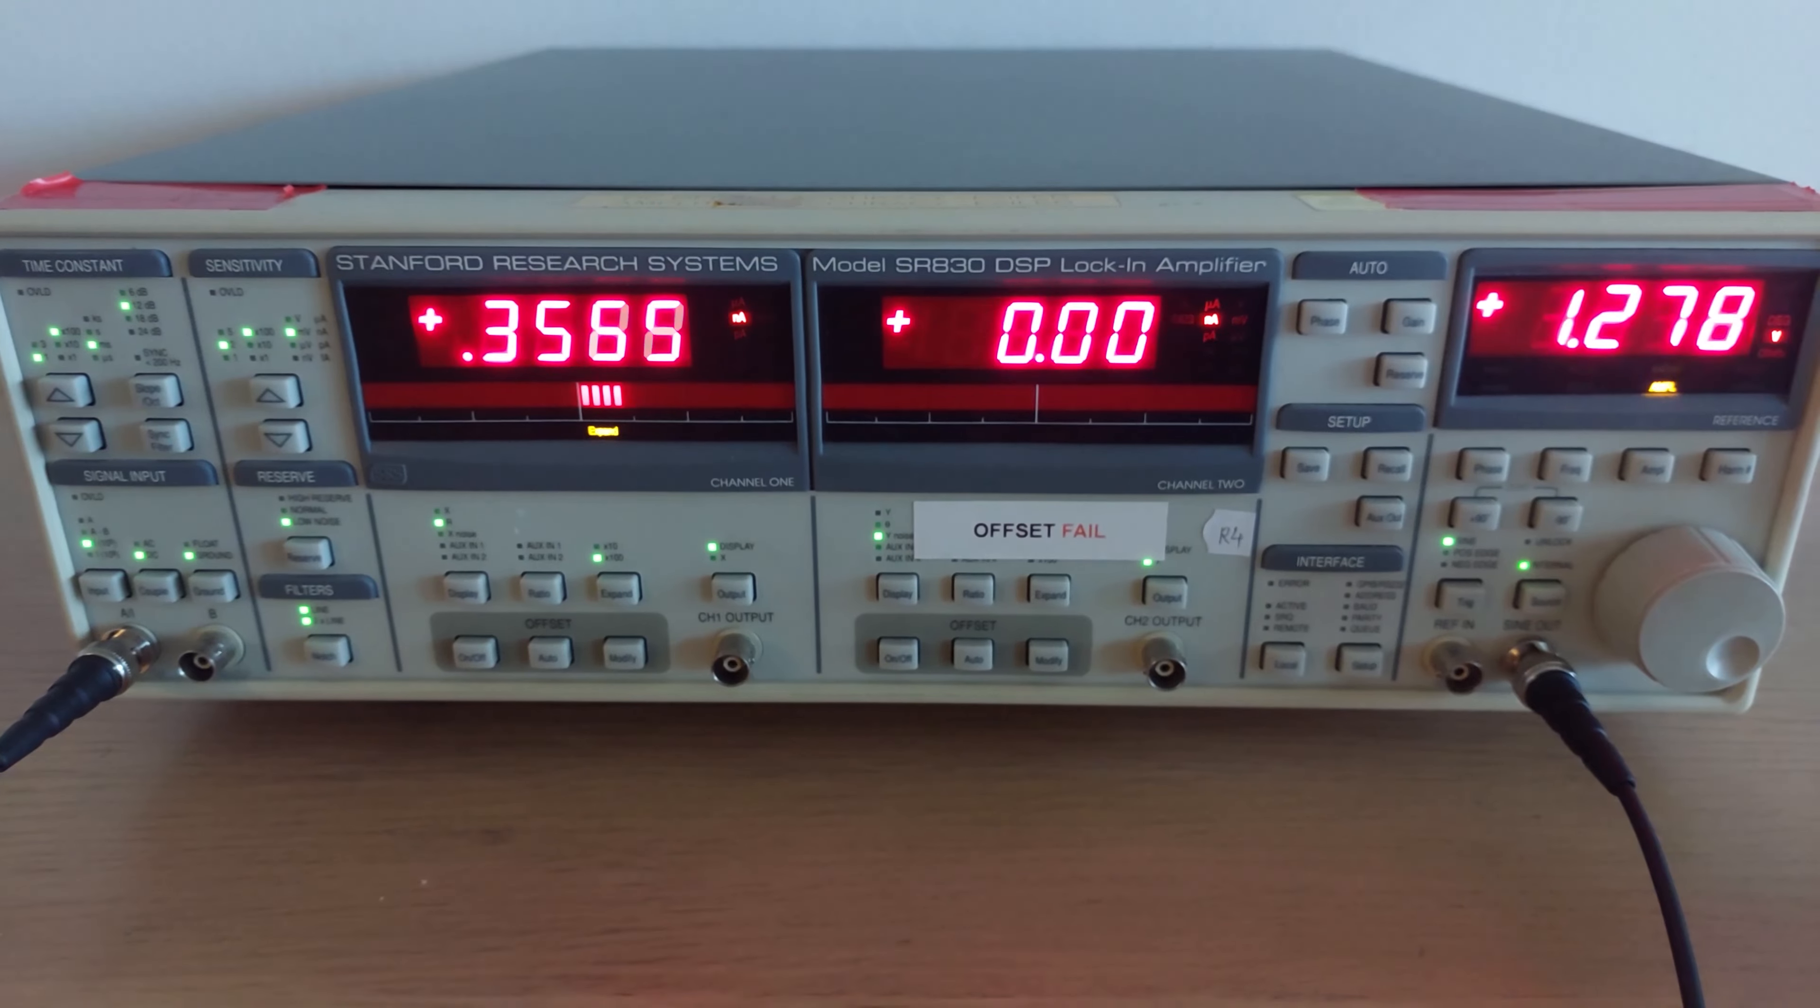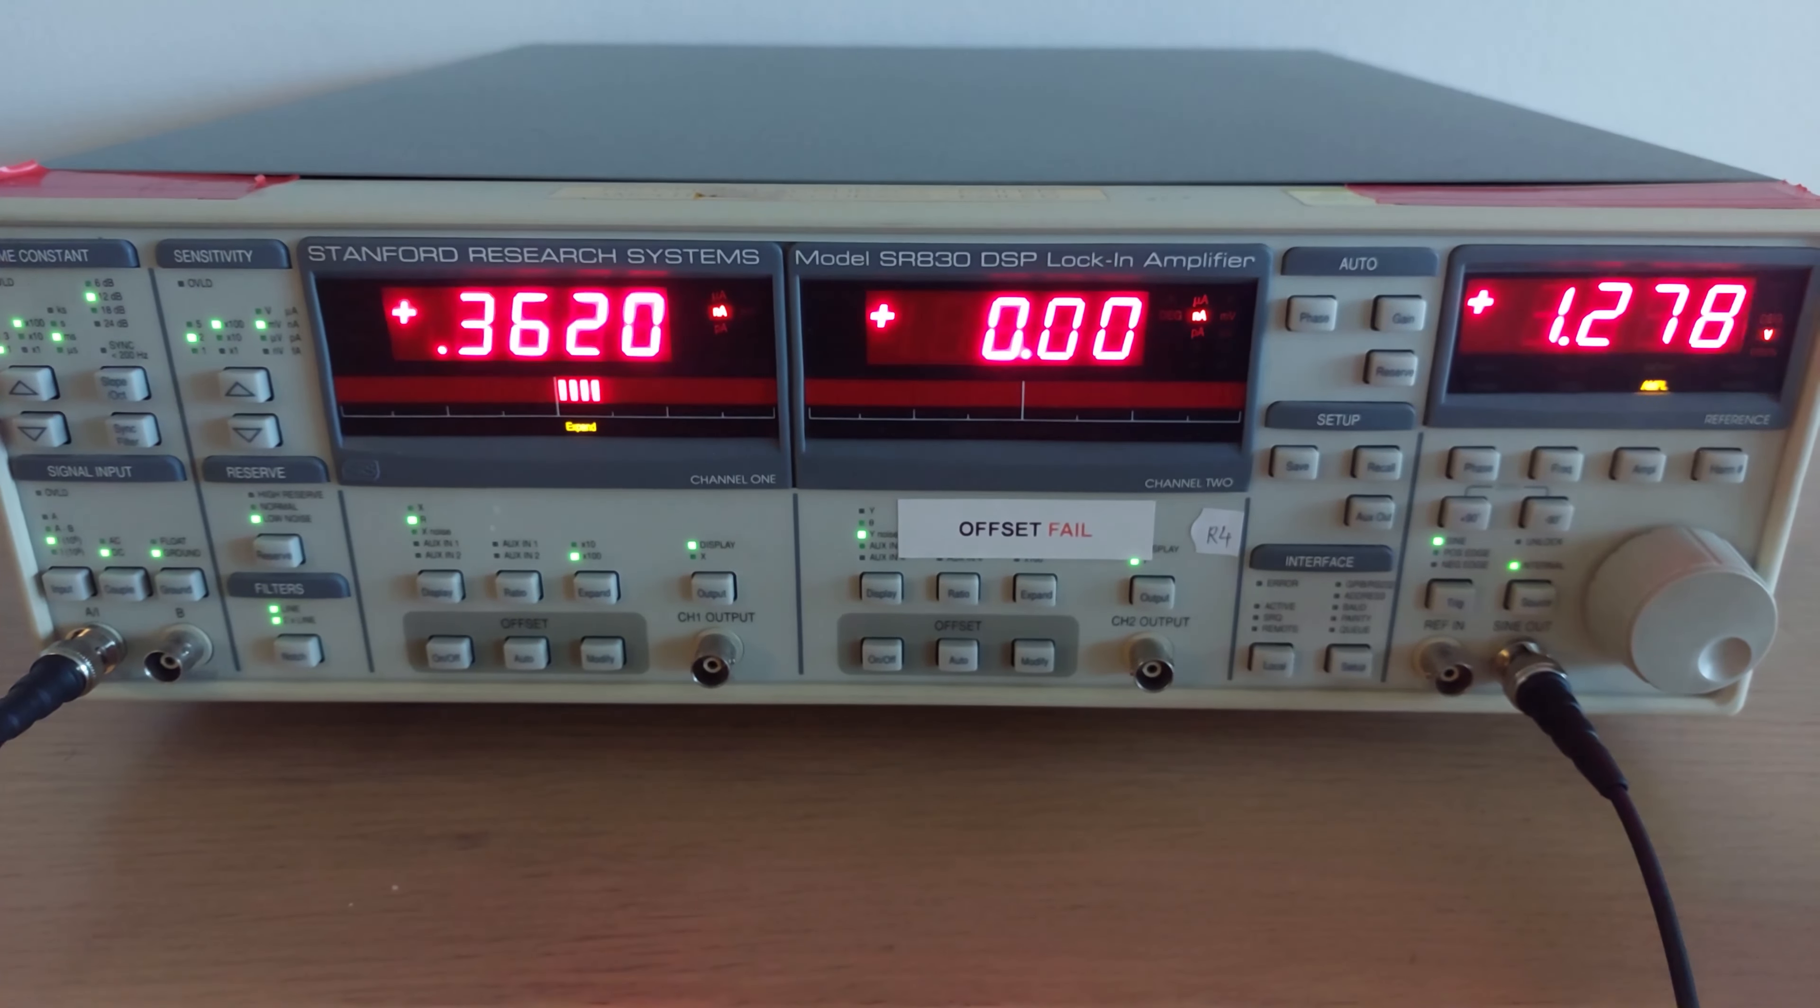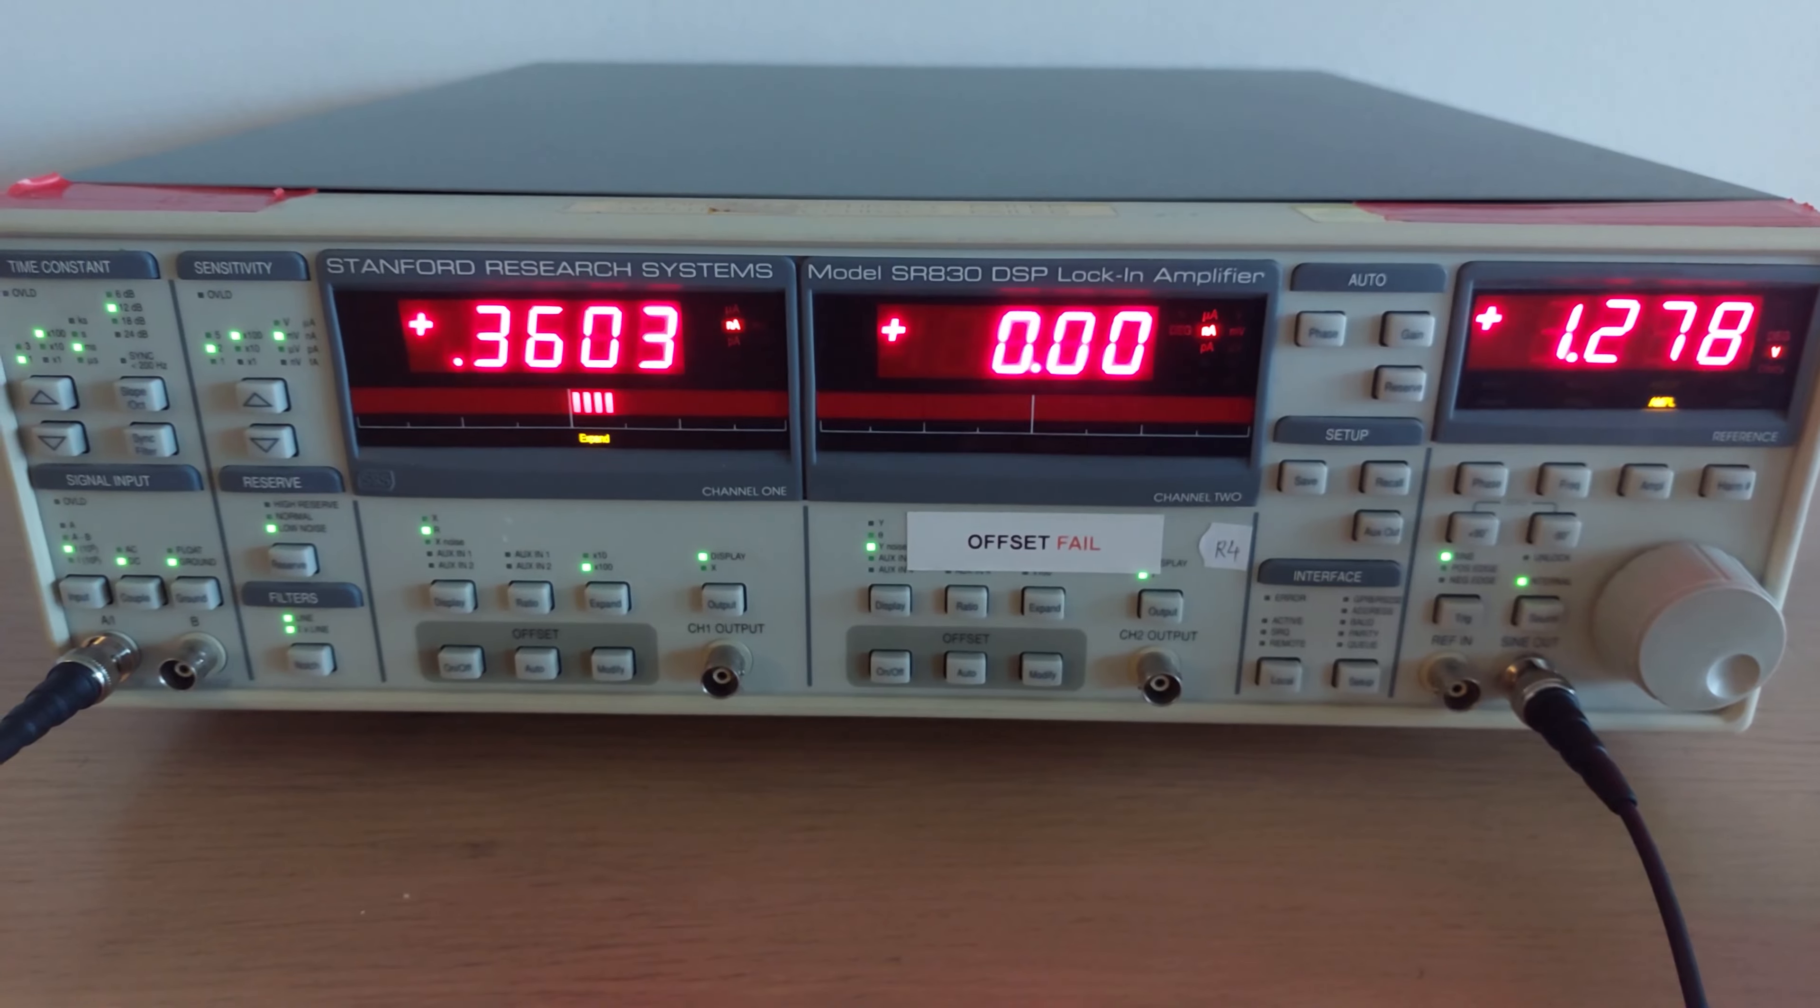It amplifies the signal by a gain of seven and then passes it through a bank of filters. Then it gets digitized and put into a DSP which synchronizes itself with the reference sine wave and filters out everything apart from any signal of that specific frequency.